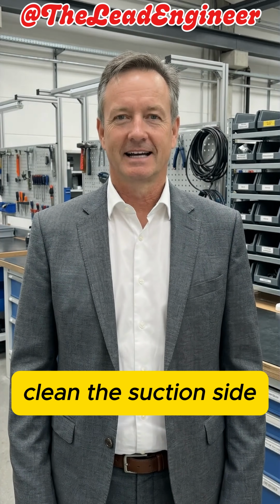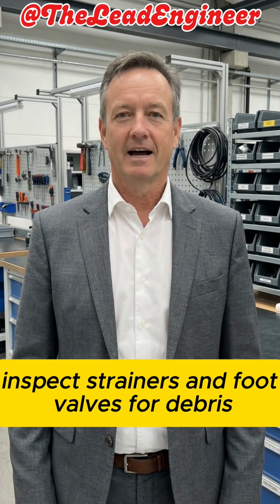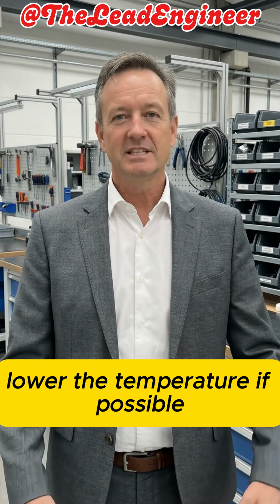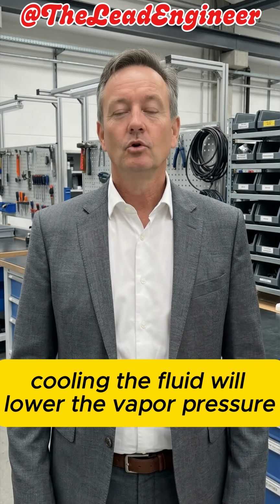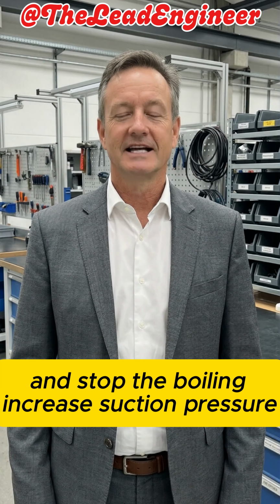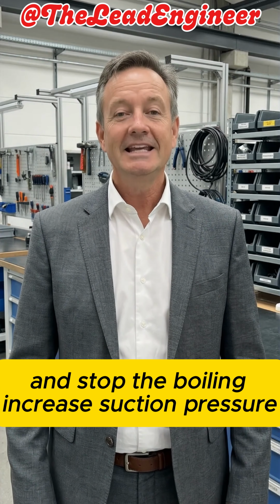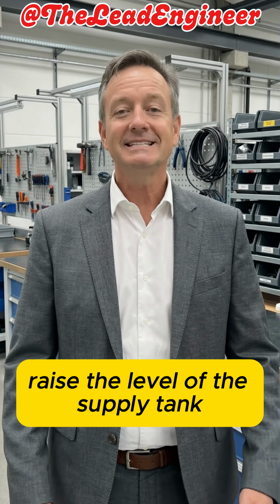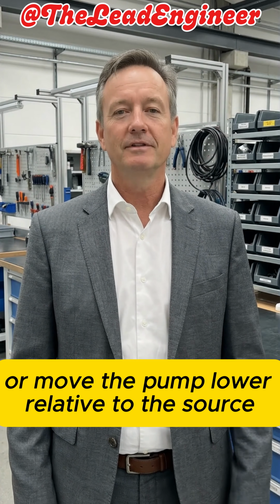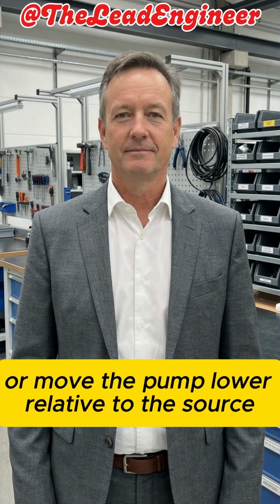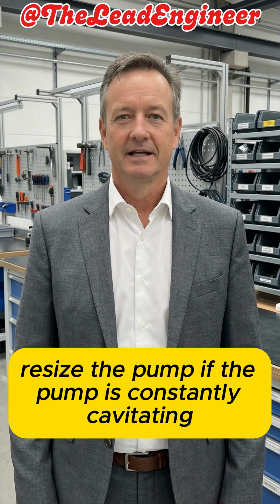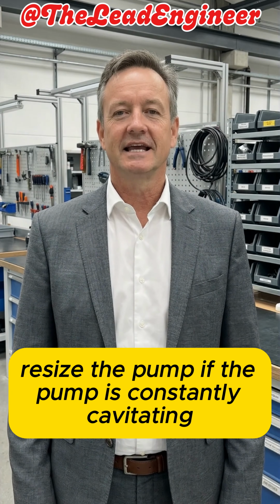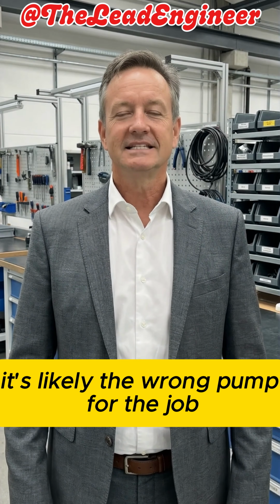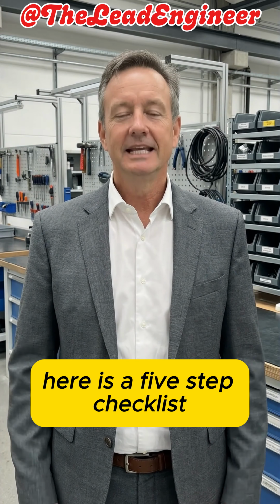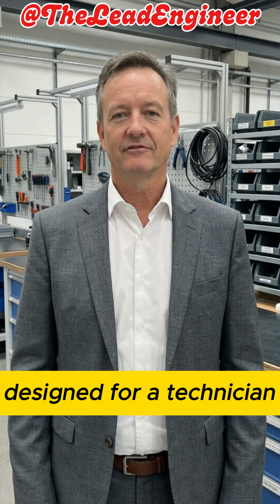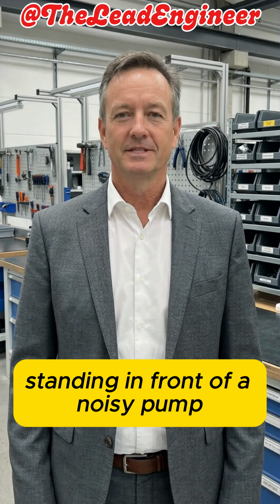Clean the suction side. Inspect strainers and foot valves for debris. Lower the temperature. If possible, cooling the fluid will lower the vapor pressure and stop the boiling. Increase suction pressure. Raise the level of the supply tank or move the pump lower relative to the source. Resize the pump. If the pump is constantly cavitating at its normal operating point, it's likely the wrong pump for the job. Here is a 5-step checklist designed for a technician standing in front of a noisy pump.